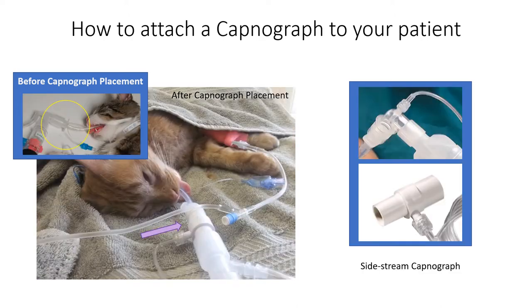We just finished reviewing a mainstream capnograph attachment. This is a side stream capnograph. As you can see, this is a smaller, lighter attachment. There are other differences that we'll discuss in a later lesson. The side stream only fits one direction, same as the mainstream we just saw. The tubing is longer for adults and shorter for pediatric patients. In the case of the side stream, this clear tubing is meant to be replaced. If the line becomes clogged, usually from condensation, this is an obvious time to replace it.